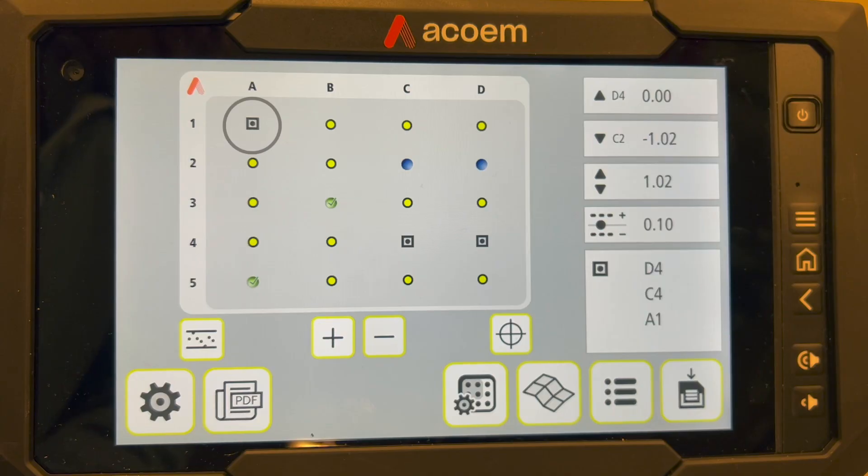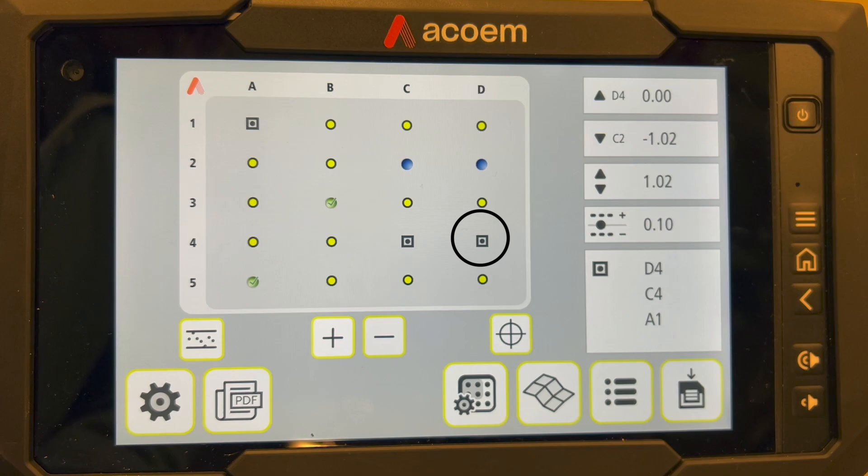Using this function, the software will automatically give us three reference points. The remaining points, which are not green, have to be adjusted using shims.